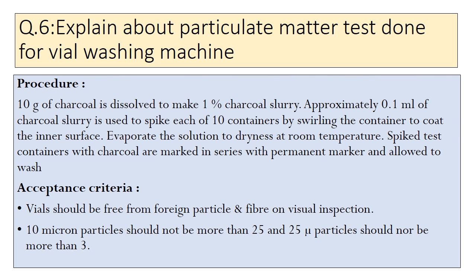The next question is: explain the particulate matter test done for the vial washing machine. In the procedure, 10 grams of charcoal is dissolved to make a 1% charcoal slurry. From this slurry, approximately 0.1 ml is used to spike each of 10 containers by swirling to coat the inner surface. Evaporation of the solution is done to dryness at room temperature. Spiked containers with charcoal are marked in series with a permanent marker and allowed to wash. Acceptance criteria: vials after washing should be free from foreign particles and fibre on visual inspection; 10-micron particles should not be more than 25, and 25-micron particles should not be more than 3.